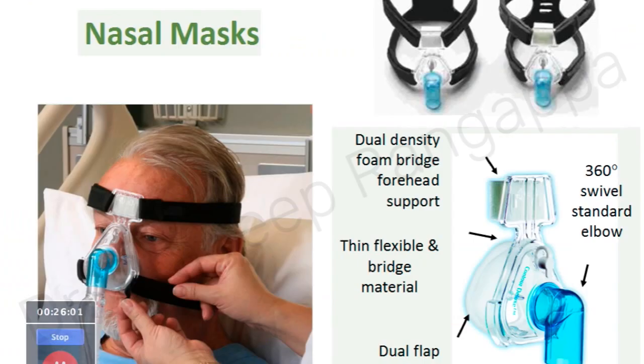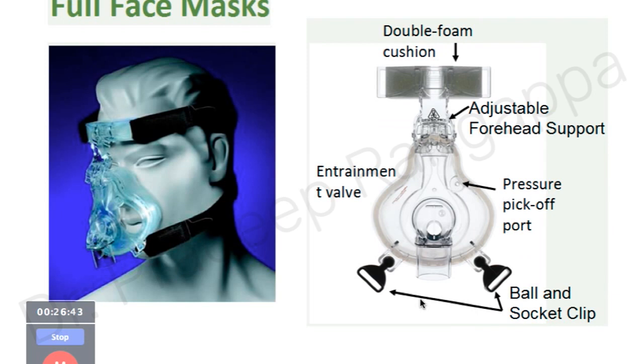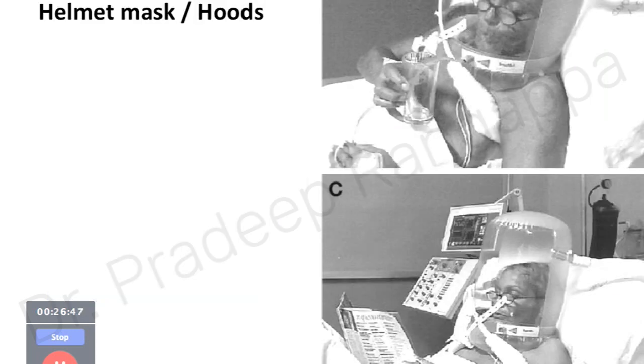There are different types of masks including nasal masks. Key mask features: the connector should have 360-degree swivel so tube kinking doesn't hamper gas delivery; foam bridges to prevent nasal bruises from high-pressure NIV; and the cushion should be thin, flexible, and dual-flap. The helmet mask or hood is more comfortable, reduces claustrophobia, and allows the patient to see. These are some features of the various NIV masks available.